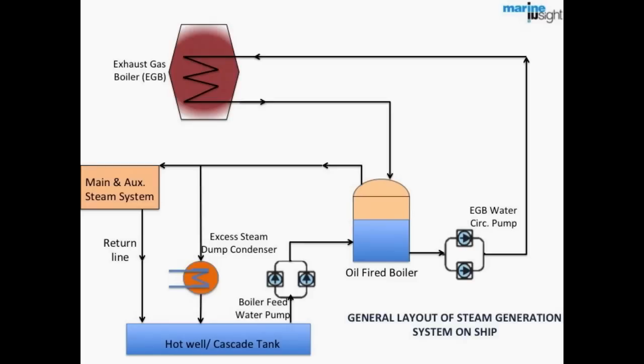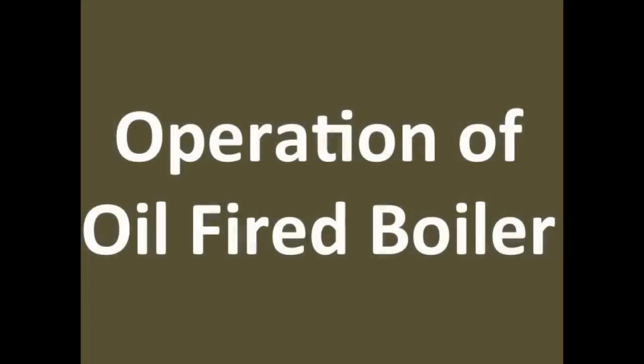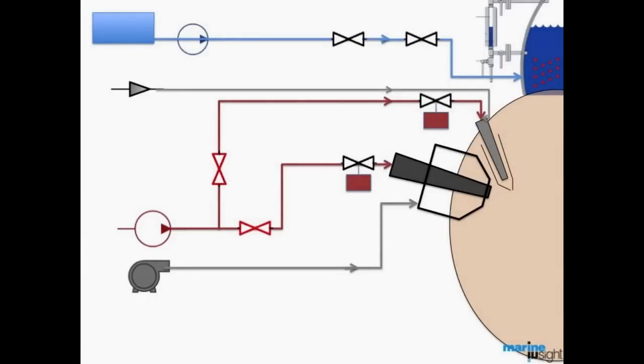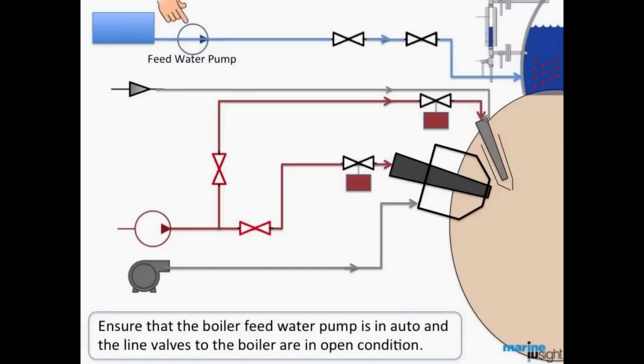This is a general layout of a steam system fitted with an exhaust gas boiler. Now we will move forward to our next section which is operation of an auxiliary oil fired boiler. Before firing a boiler, ensure that the boiler feed water pump is in auto and the feed water line valves to the boiler are in open condition.